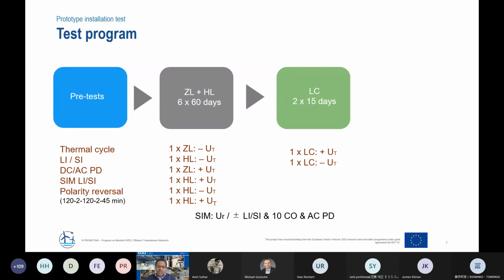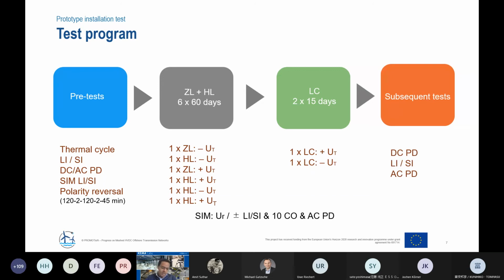In reality, the current is not either zero or full rated value, but it varies depending on the power flow in the system. So we try to mimic that with a load cycle, where for some hours of the day it is fully loaded, or reduced, or maybe less loaded. So this has been performed for the 2 polarities, each polarity lasting for 15 days. I come back to this later. And then, of course, subsequent tests, which means after finishing the whole test, we check if everything is intact by applying different measurements, different impulses. And that's also followed by visual inspection after dismantling of the test object.